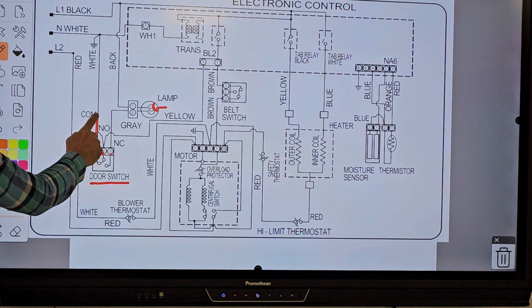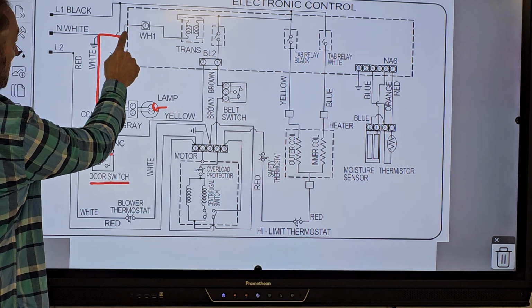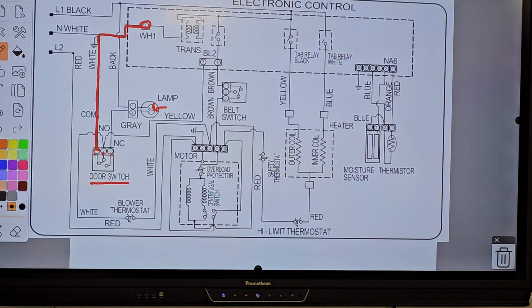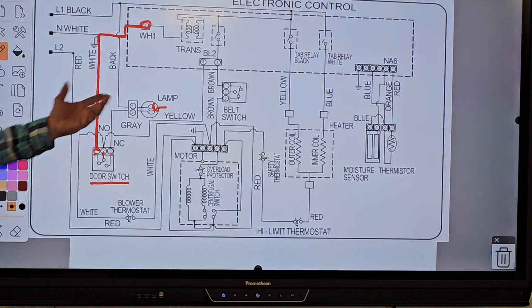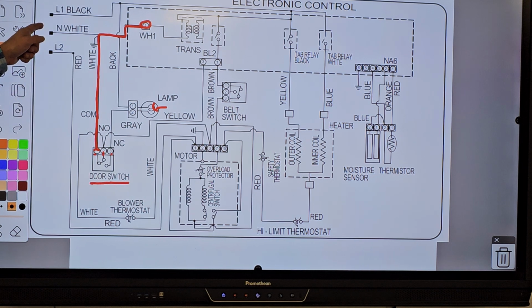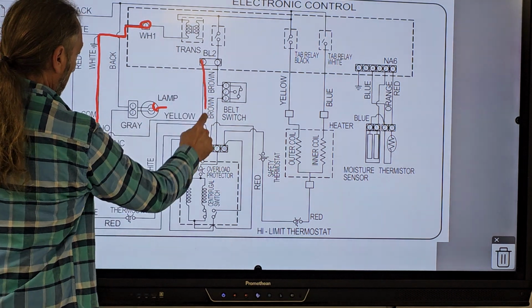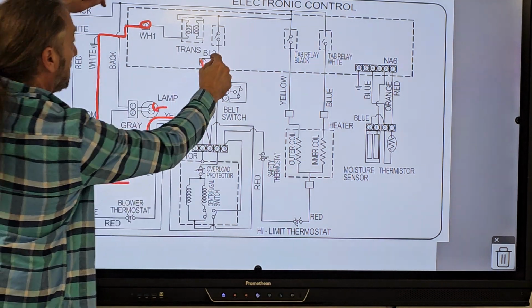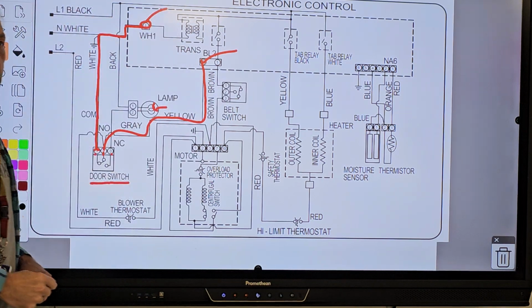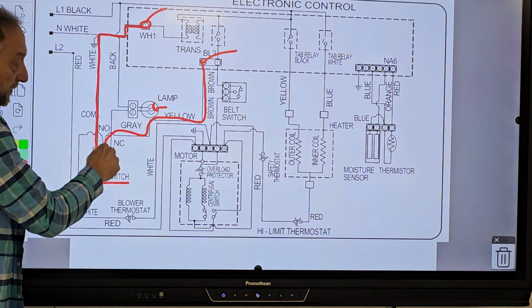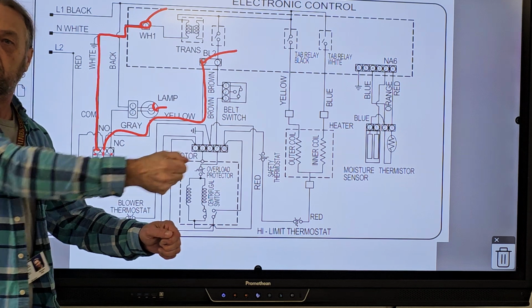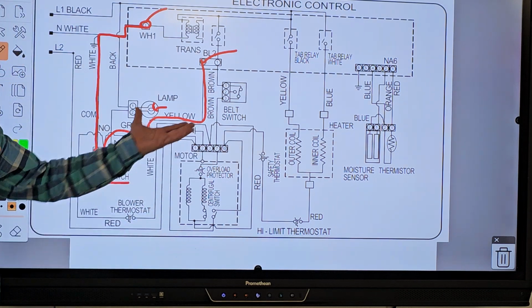So WH1, could be BL2. Right there, pin 1, a white wire. Is that where that wire goes? Yep, or the power cord in the back of the machine. But what about pin number 2? BL2, pin 3. So you would put your meter here, and using the wires of the machine, I can open and close the door to see if it's working.